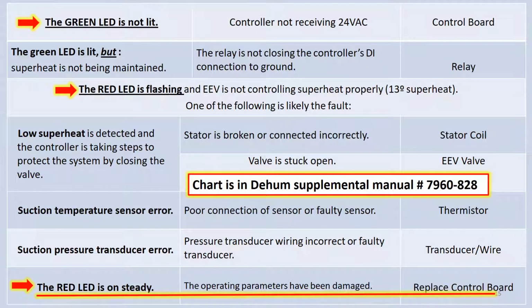This is the troubleshooting chart that appears in the manual. I put some arrows up here on the indicator lights. The solid green LED is on whenever there's 24 volts on the board. The flashing red LED is indicating that one of the faults has occurred and the control has closed the valve. The red constant on LED indicates operating parameters of the control have been damaged in the board and the board has to be replaced.